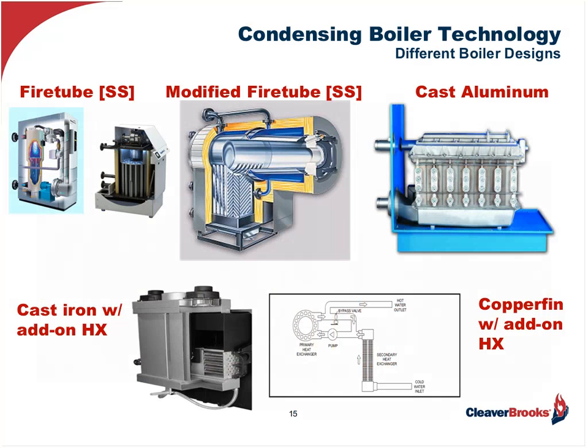So, a little bit about condensing boilers. First off, there's several different types out there. And by the way, condensing boilers have been out since the early 90s. Sometimes people confuse them with near-condensing modular boilers, and they're not the same. So, the types of boilers out there are the fire tube, the modified fire tube, the cast aluminum. There are also cast iron boilers, which are really those modular boilers, but to allow them to operate in the condensing mode, they did an add-on heat exchanger. And the same is true with the copper fin boilers, and I'm sure a lot of you have seen those in the past. Because copper will corrode, they did an add-on heat exchanger. For all these boilers where the corrosion occurs, we've gone to stainless steel so that it doesn't affect the life of the boiler.